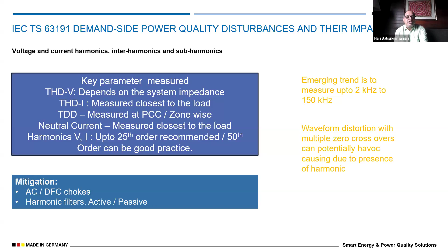Another important point is that harmonics can distort the waveforms very badly, as we all know, causing multiple zero crossovers. Whenever the waveform crosses zero, because of the distortion, it will do multiple zero crossovers, and that can become very bad for the system, because all our systems are designed for a pure sine wave, which means 100 crossovers a second. If we have more than 100 crossovers, our electronic equipment and drives don't know where they are, and they can potentially create much more problems than envisaged.